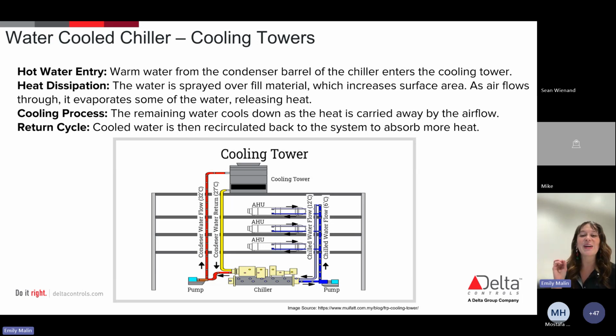But we're going to think of another anecdote for a water-cooled chiller system as a restaurant kitchen. So if you think about it like that, the chiller is going to be the refrigerator. It's keeping all of its contents cold, so it's keeping the water cooler. The cooling tower itself is going to be one of those big exhaust fans that's getting rid of all of the heat from inside of this kitchen. The pumps within this system are going to be like our wait staff. They're running back and forth, bringing that food to and from the refrigerator to all of those tables. So think of that like the pump is bringing the water from that cooling tower to the zone, right?